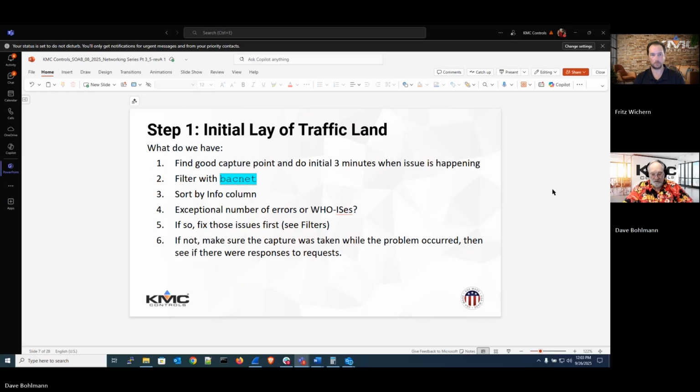When you open up Wireshark, there are filters, and we'll do that here in a minute. The first filter I mentioned here again is just BACnet. You only need to put that in there if it's BACnet over IP. When you do a Wireshark using our 5051 router, it will capture MSTP, and you do not need this filter. Everything in there is BACnet.